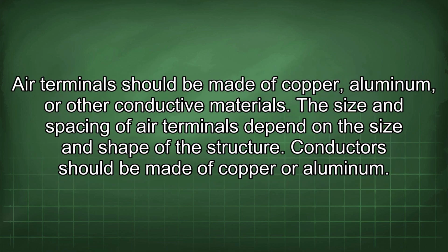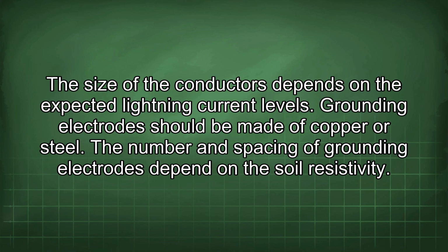Air terminals should be made of copper, aluminum, or other conductive materials. The size and spacing of air terminals depend on the size and shape of the structure. Conductors should be made of copper or aluminum. The size of the conductors depends on the expected lightning current levels. Grounding electrodes should be made of copper or steel. The number and spacing of grounding electrodes depend on the soil resistivity.